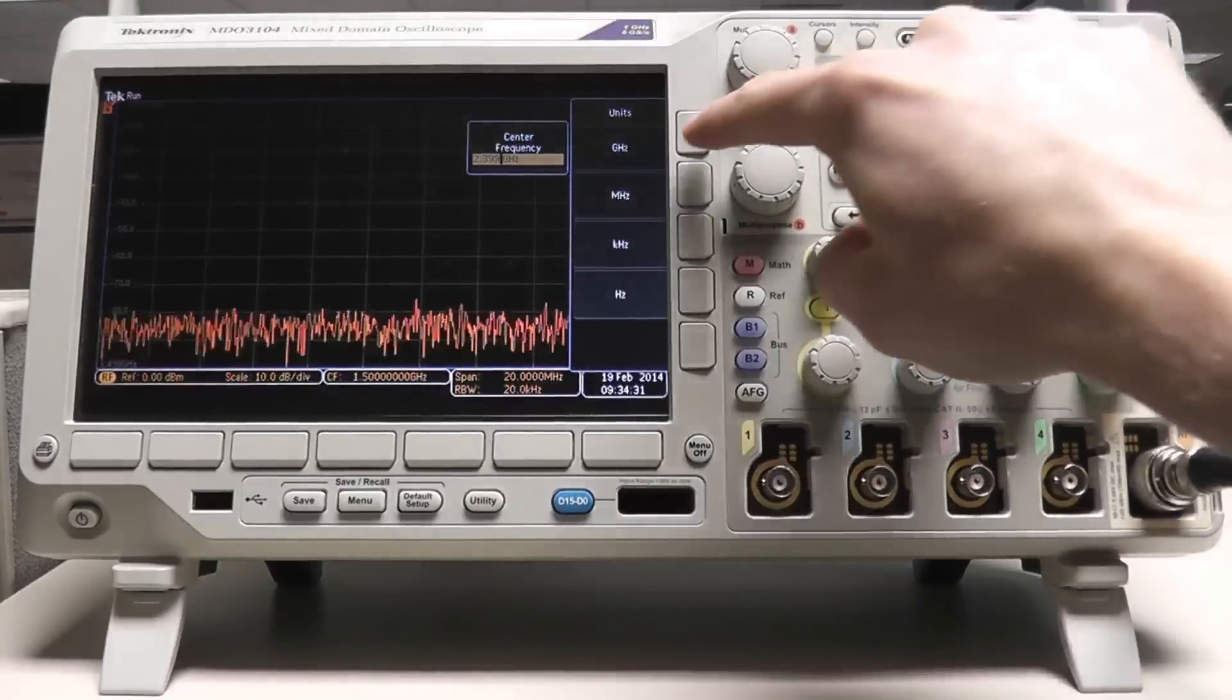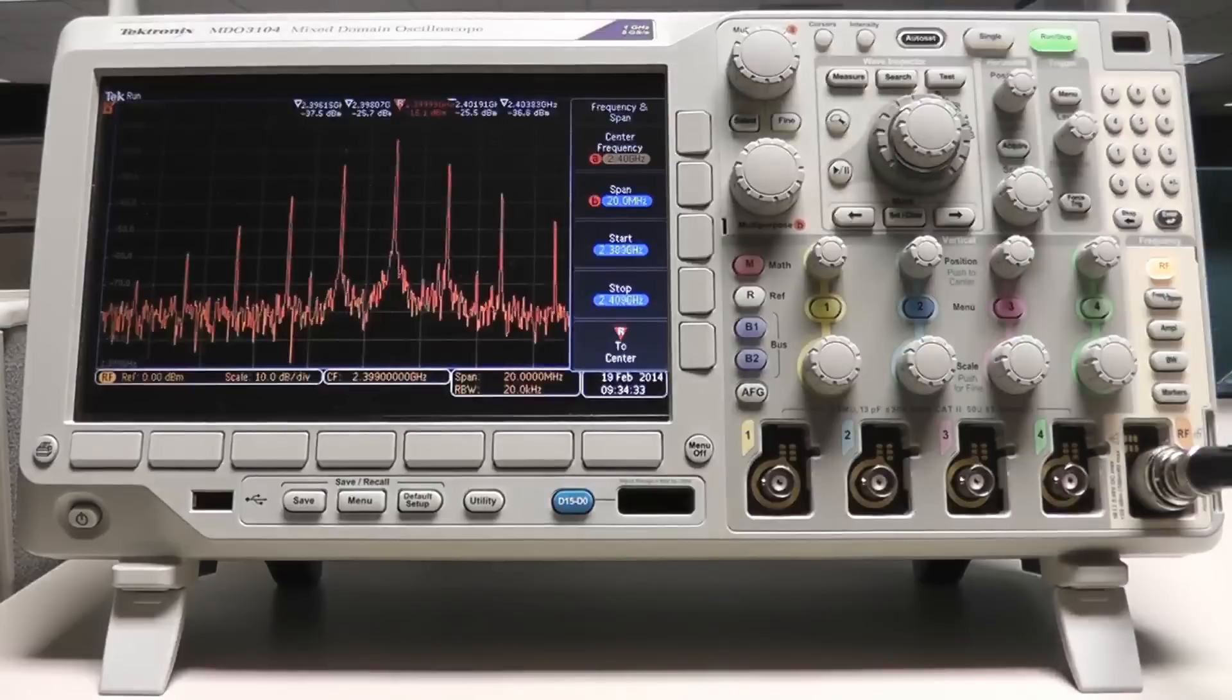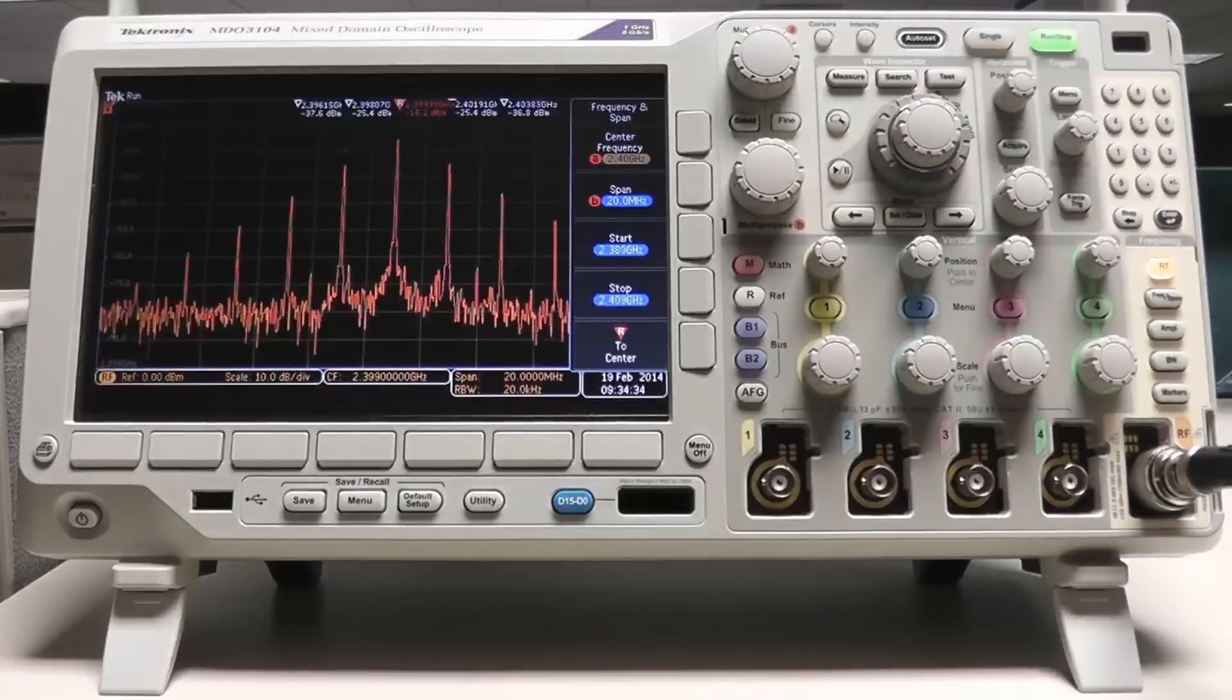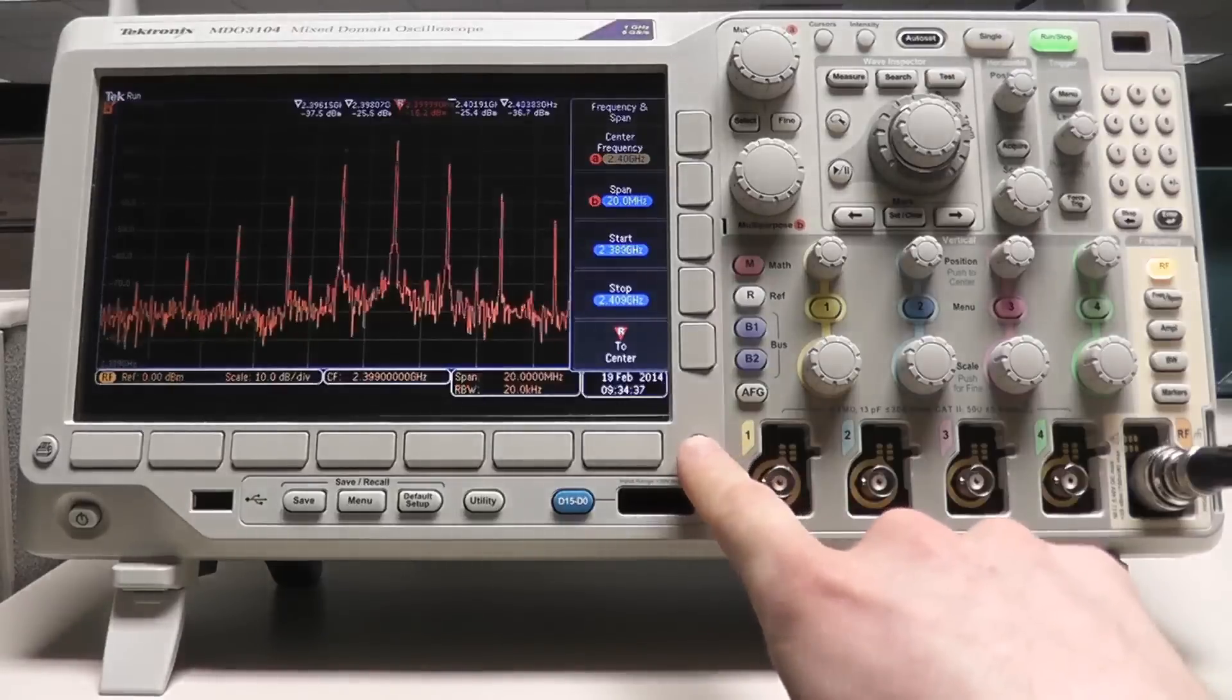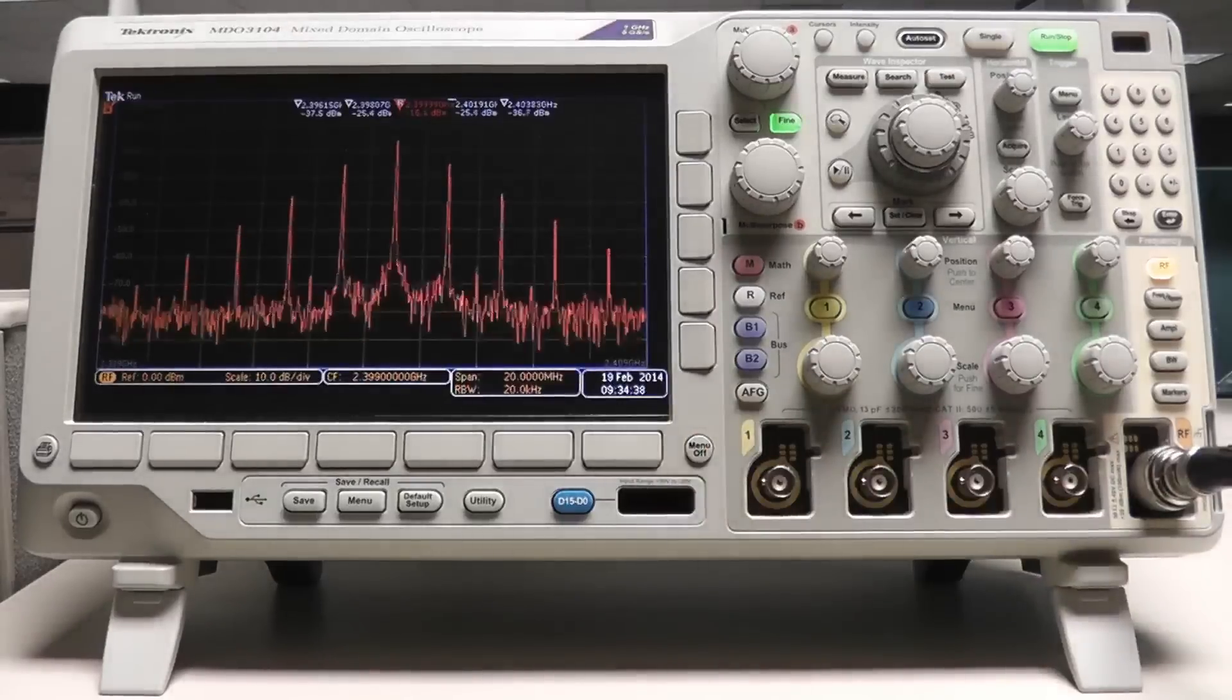Notice that the peaks are automatically marked by the MDO with frequency and amplitude information. The markers can be configured in the marker menu.